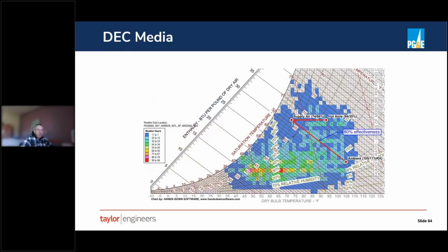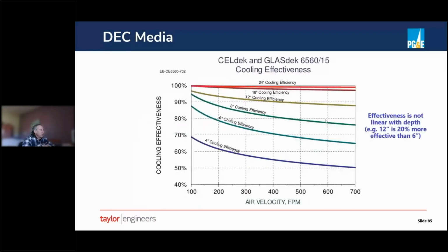And psychrometrically, this is what direct evap looks like. Here, if your ambient temperature, for example, is 105 degrees in Phoenix and happens to be at 11% RH at this point here, running it through that media can cool it down to 74 degrees, for example, and potentially even lower depending on the effectiveness of your media. But this was the design temperature, so you would only take it down as low as you needed. And then as it goes through your data center, it gets heated up and returned back from your hot aisle at some higher temperature.